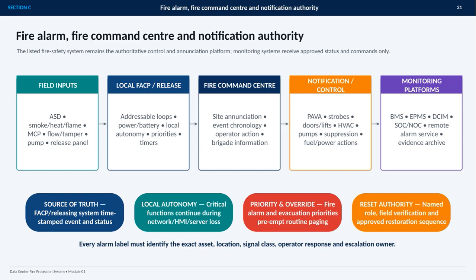Notification and control functions may include voice evacuation, strobes, doors and lifts, HVAC, pumps, suppression, and fuel or power actions. Monitoring platforms such as BMS, EPMS, DCIM, SOC or NOC systems, remote alarm services, and evidence archives receive approved status and commands. They do not replace the authoritative fire system. Critical functions must continue through network, HMI, or server loss. Fire and evacuation priorities override routine paging, and reset requires a named role, field verification, and an approved restoration sequence. Every alarm label must identify the exact asset, location, signal class, response, and escalation owner.